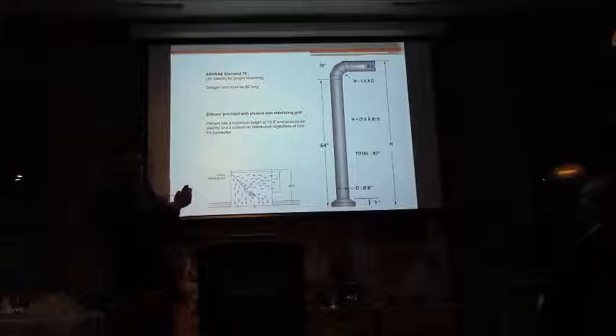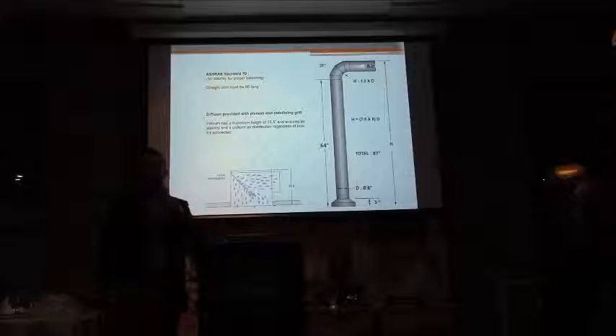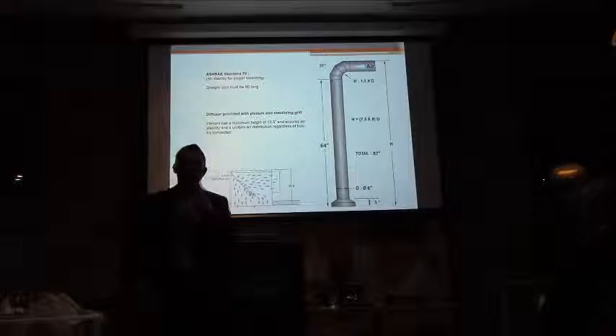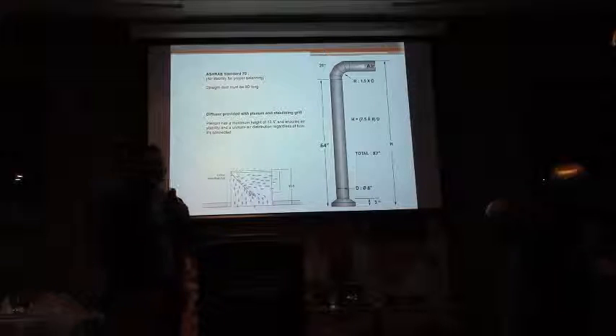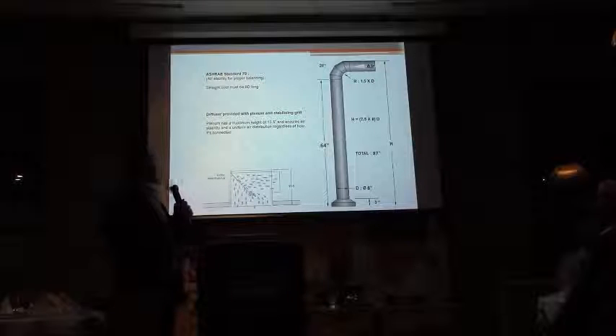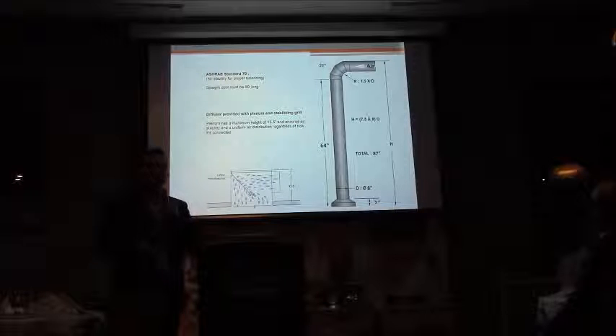Have you ever seen a job site with 64 inches inside the ceiling area? Nope. Has somebody ever seen it? Raise your hands. It was an accident. So whenever you open any catalog of any North American manufacturer and you look at the sound values, the throw values, the static pressure losses, these values are based on these lab conditions.